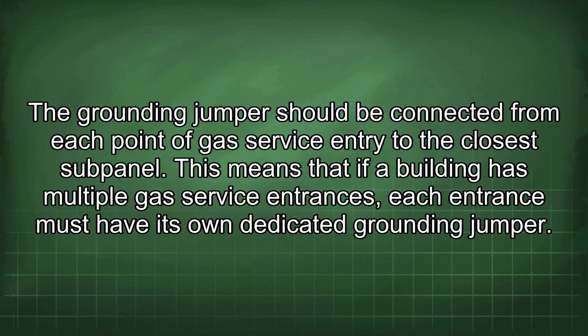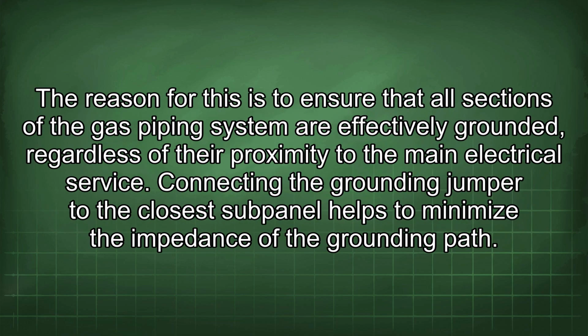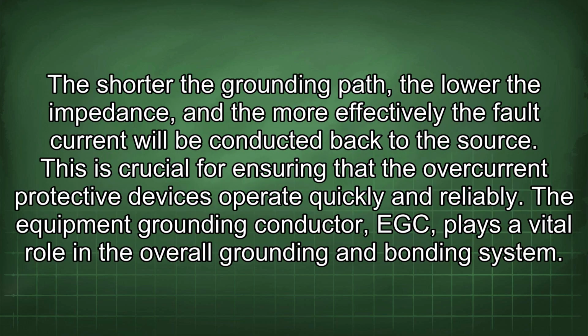The grounding jumper should be connected from each point of gas service entry to the closest subpanel. This means that if a building has multiple gas service entrances, each entrance must have its own dedicated grounding jumper. The reason for this is to ensure that all sections of the gas piping system are effectively grounded, regardless of their proximity to the main electrical service. Connecting the grounding jumper to the closest subpanel helps to minimize the impedance of the grounding path. The shorter the grounding path, the lower the impedance, and the more effectively the fault current will be conducted back to the source. This is crucial for ensuring that the overcurrent protective devices operate quickly and reliably.